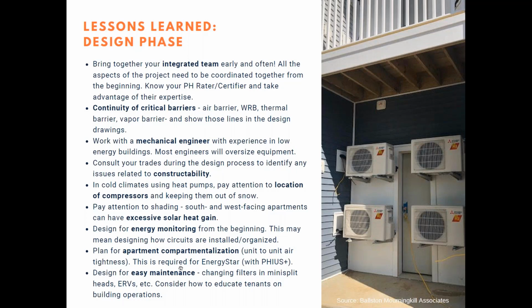Or at least checked on that kind of basis. So think about, in these apartment buildings, how you're going to have access into the units if you have to change filters. Or how can you design it so the filters are accessible from the mechanical room or common space, to make it easier for the maintenance staff. That's definitely something to think about. Some of the biggest failures we've seen are when those filters have never been changed, and you realize the reason you're not getting any heat is that it's totally clogged up with cat hair or something crazy.